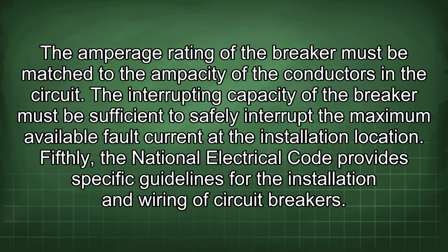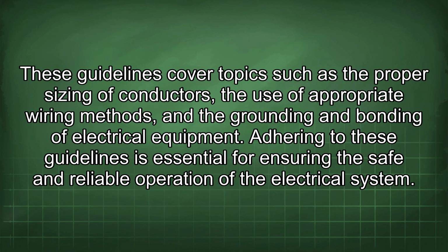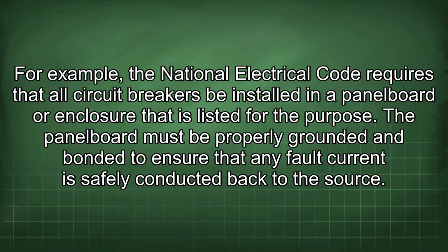Fifthly, the National Electrical Code provides specific guidelines for the installation and wiring of circuit breakers. These guidelines cover topics such as the proper sizing of conductors, the use of appropriate wiring methods, and the grounding and bonding of electrical equipment. Adhering to these guidelines is essential for ensuring the safe and reliable operation of the electrical system. For example, the National Electrical Code requires that all circuit breakers be installed in a panel board or enclosure that is listed for the purpose. The panel board must be properly grounded and bonded to ensure that any fault current is safely conducted back to the source.